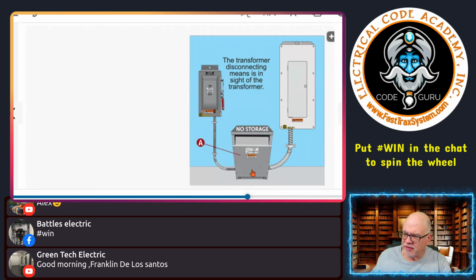Now, in this case right here, one of the questions I get from people, if this is like an FMC right here, chances are the sizes of this are larger, and this FMC is not to be used as any type of equipment bonding jumper or anything like that. There's no overcurrent protection device here. So typically your supply side bonding jumper would be either in here or it's permitted to be in here. Typically not both, because now we have a metallic path between them, right? So again, it's either here or here. Either way, you're required to have it running through here, and it's going to be basically an equipment bonding jumper or supply side bonding jumper on the supply side of this panel here.